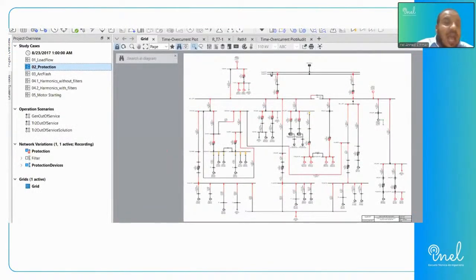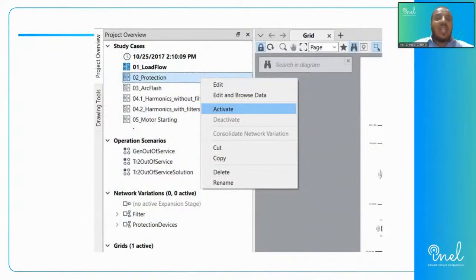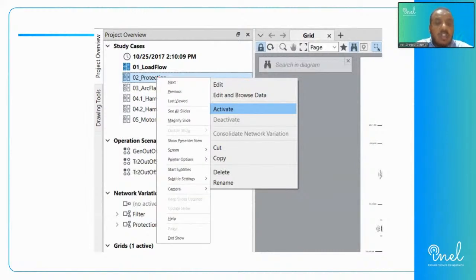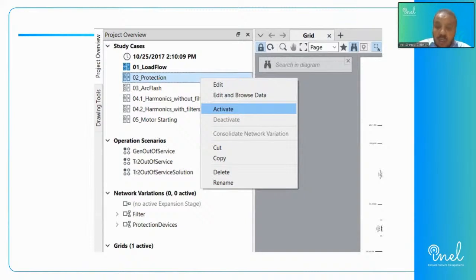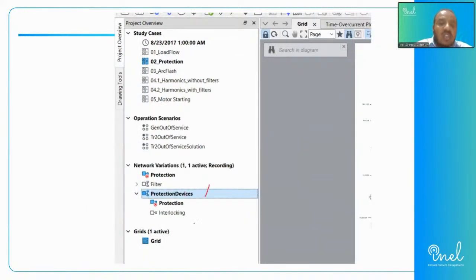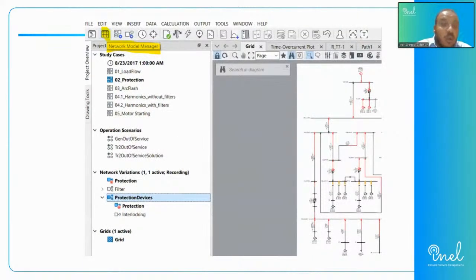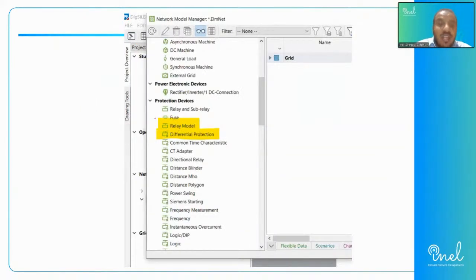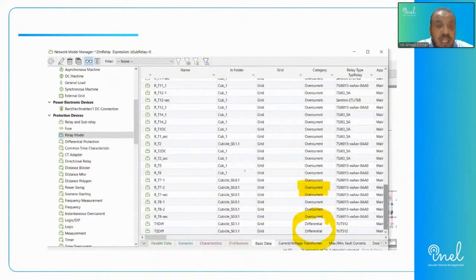And from there, we can activate our protection analysis. If you right-click on the protection tab here in the case study and activate it, you will find that many protection devices are activated. And from there, we can open the relay model data to the network model. In your system, you can apply either a different model for the relay or the differential protection, which is our focus for today. Our focus is the differential relay, and in the library of relay models you will find many different types of overcurrent relay and some types of differential relay.